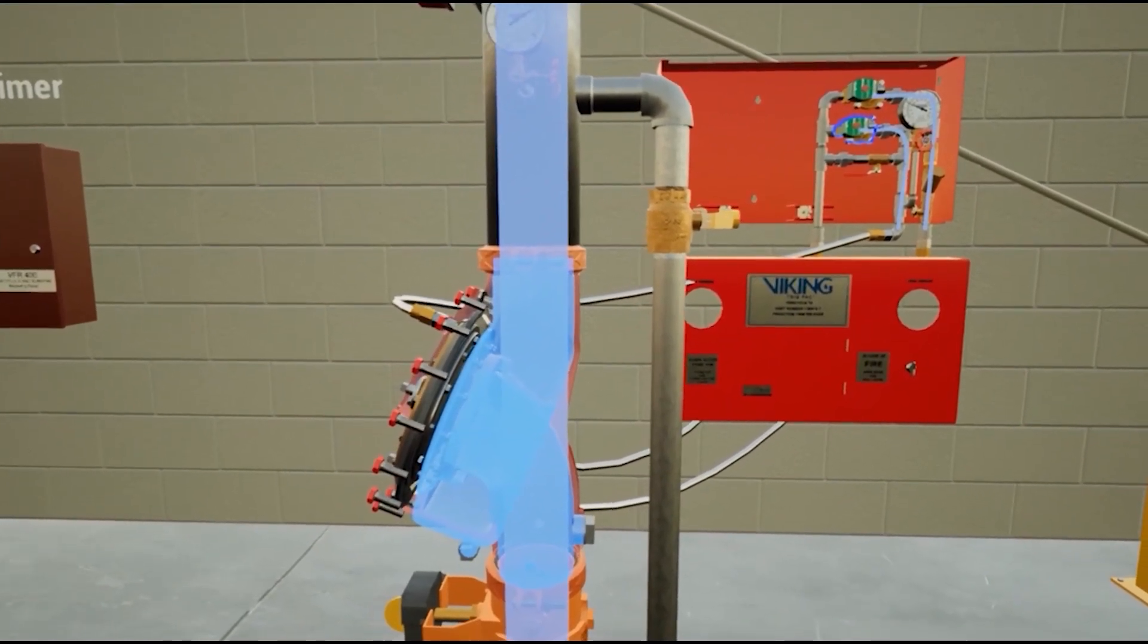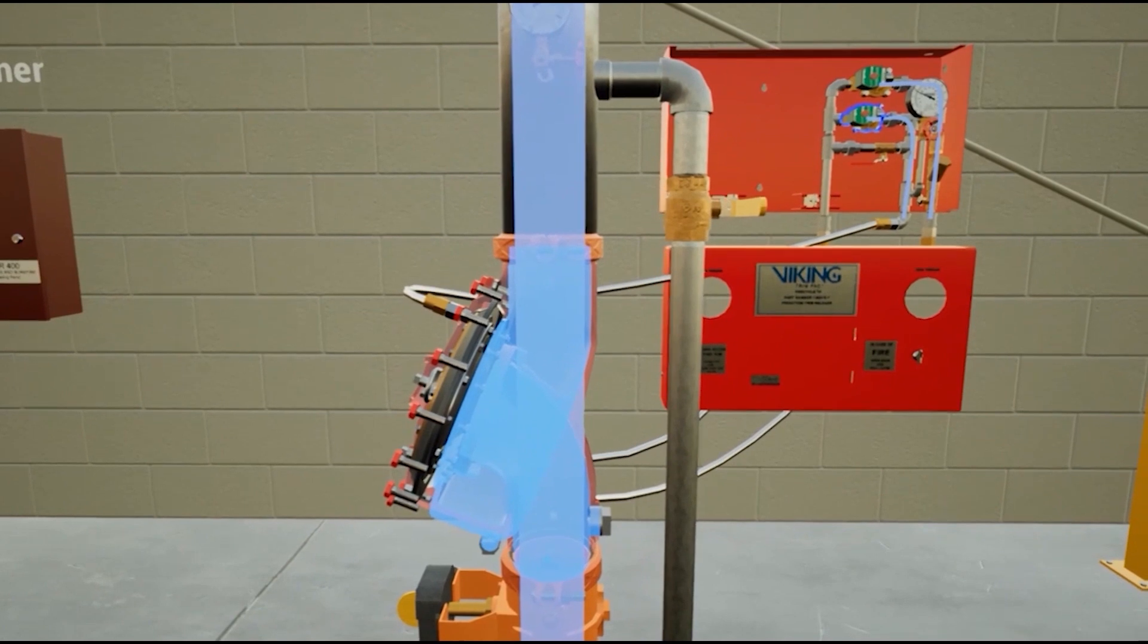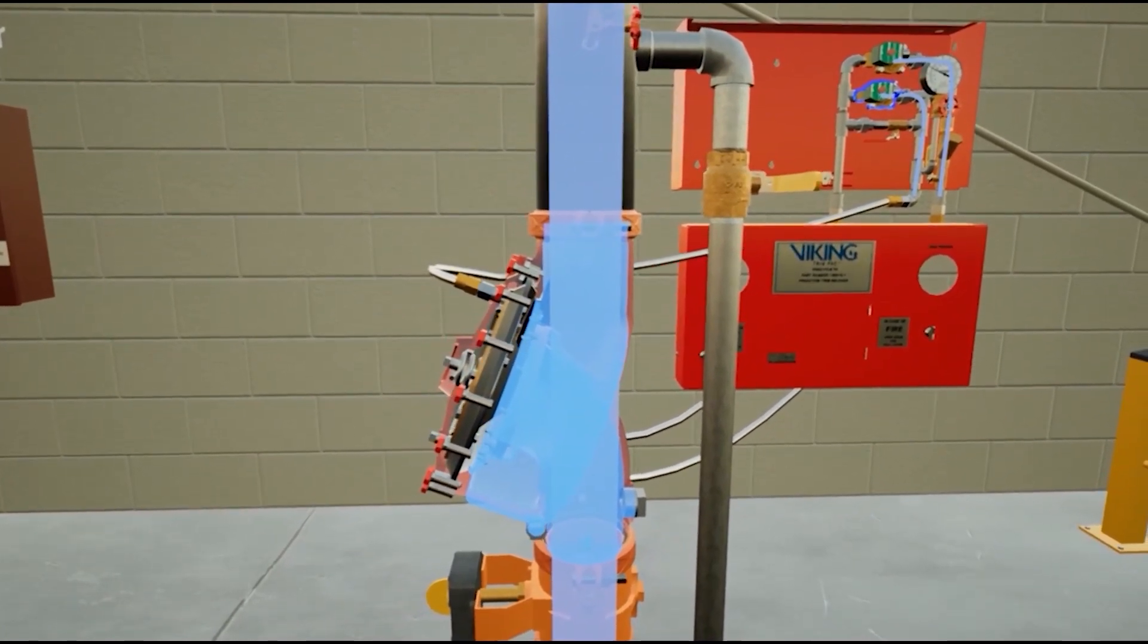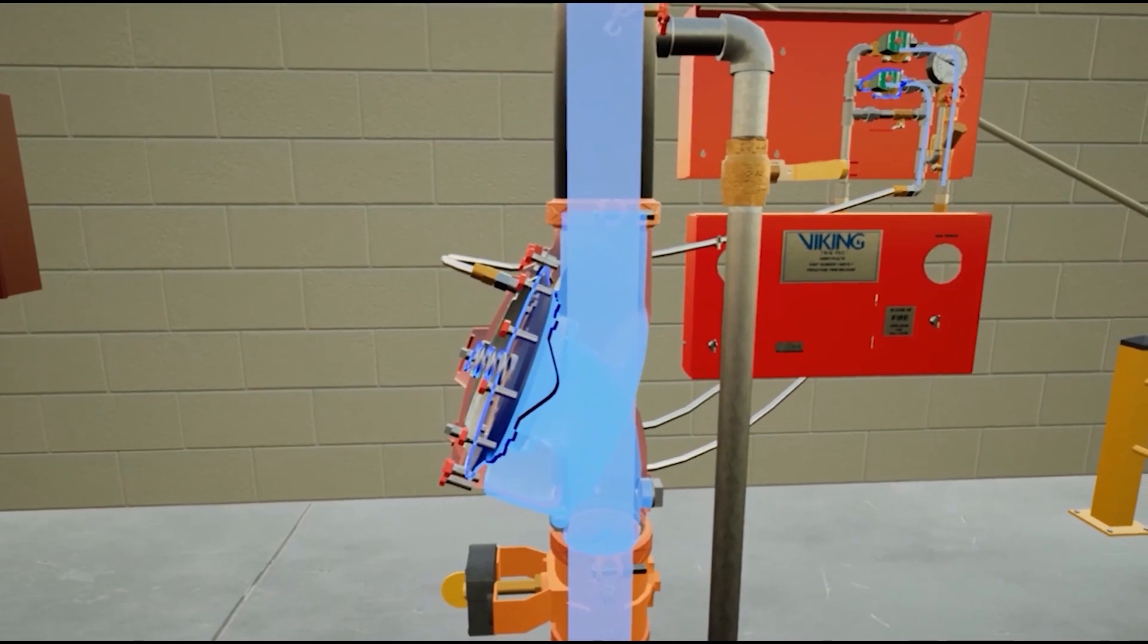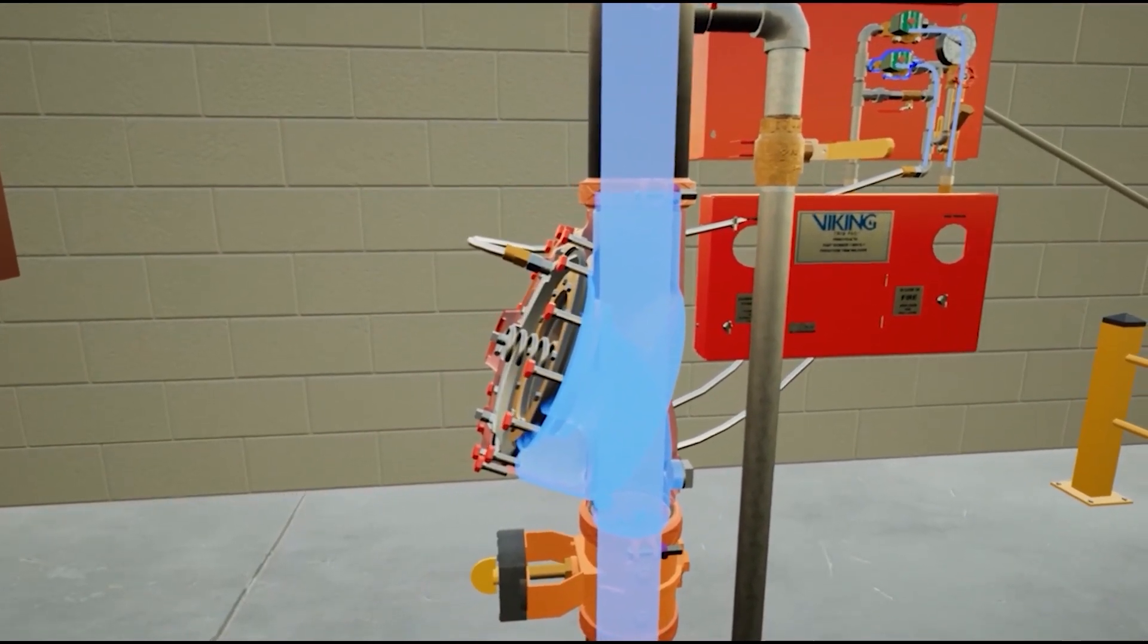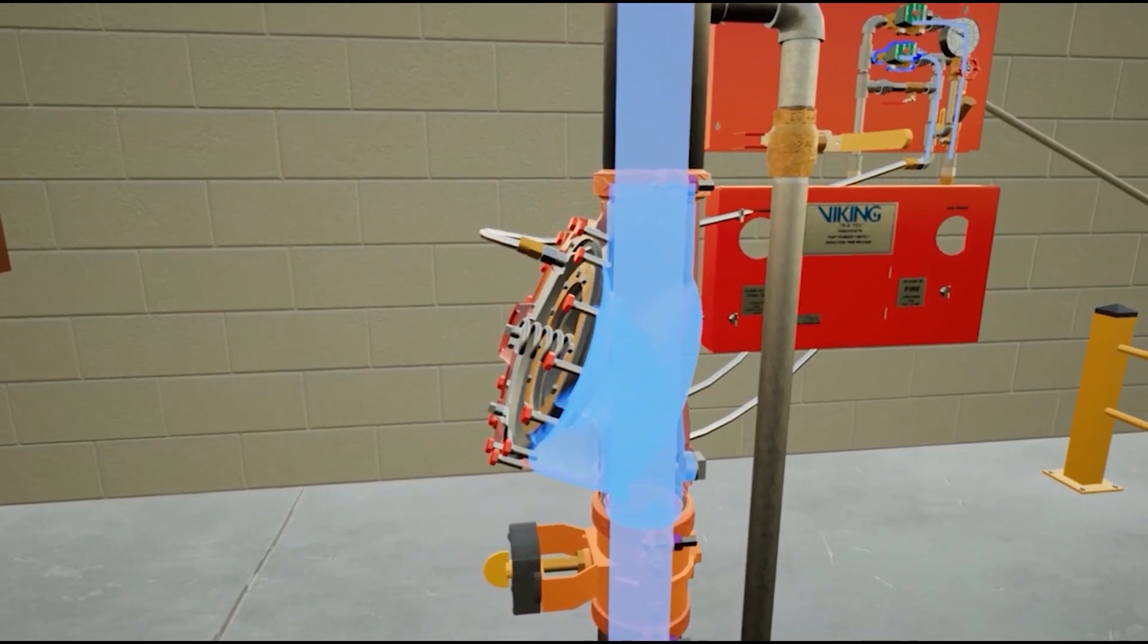Once priming pressure is established in the prime chamber, in conjunction with the spring assist within the flow control valve, the clapper will close against the seat, stopping the water flow through the system.